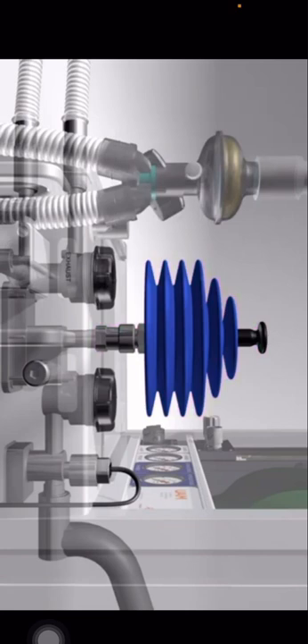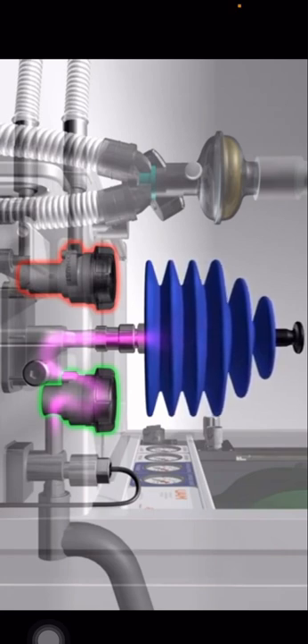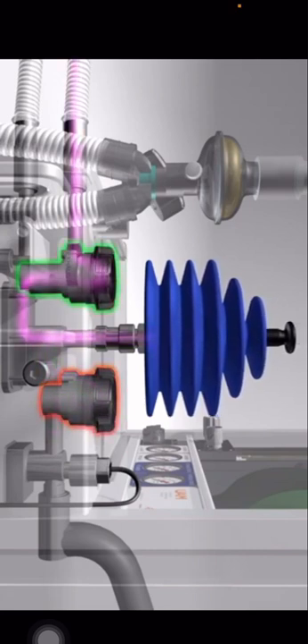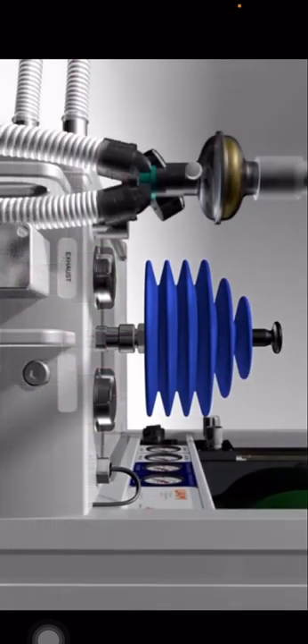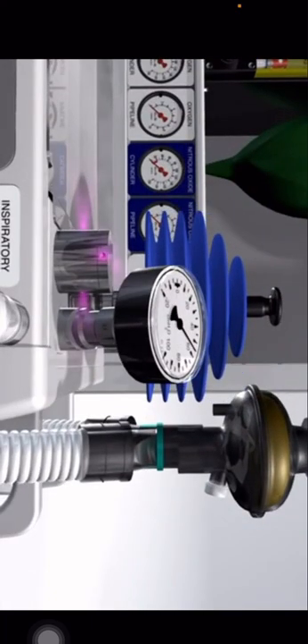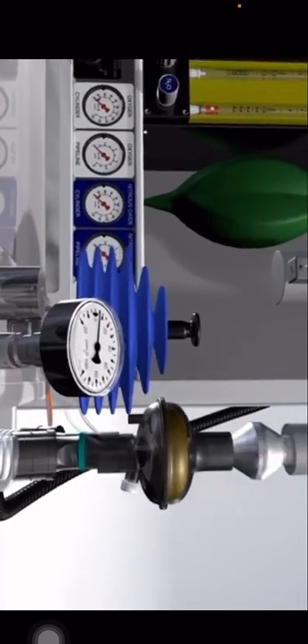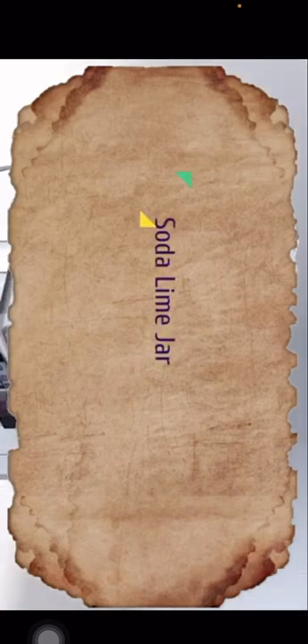The second type is the draw-over vaporizer, which is driven by the patient's respiratory effort. Gas flow performance depends on the patient's minute volume. The draw-over vaporizer is much simpler in design and may be used with liquid volatile agents including older agents such as diethyl ether and chloroform, although these can be dangerous. Because performance is so variable, accurate calibration is impossible.